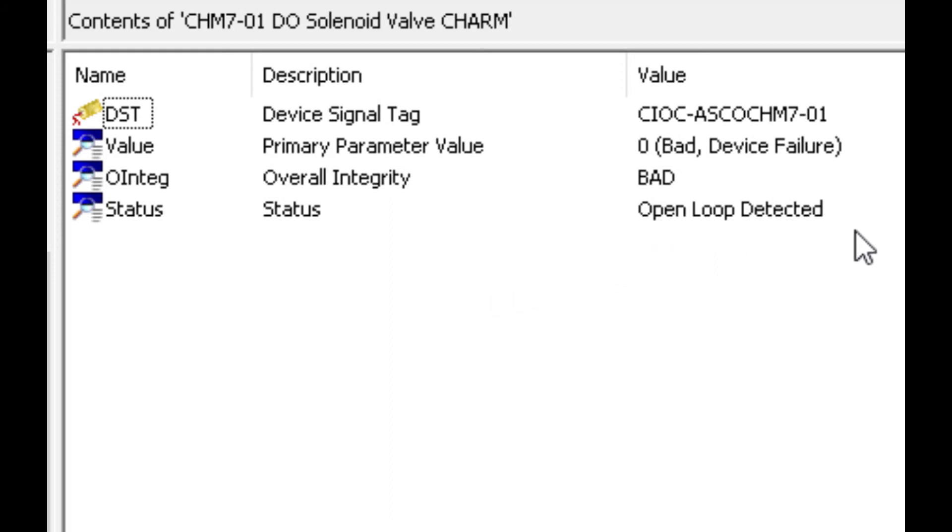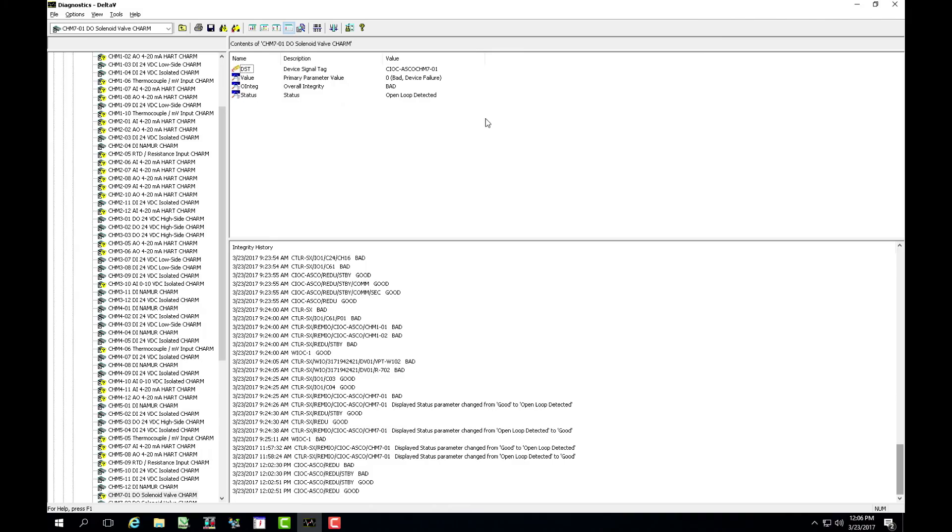And we can actually see that an open loop is detected and this is how the diagnostics in the ASCO 580 charm node is natively integrated into Delta V. There's no configuration necessary and it shows here an open loop detected which indicates that there's an open coil in the solenoid valve.